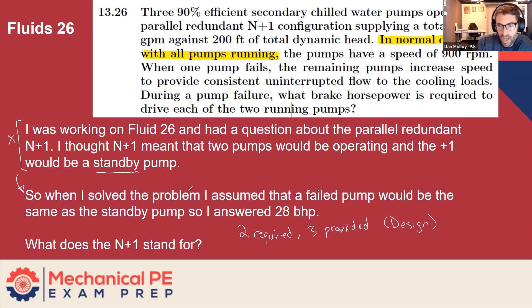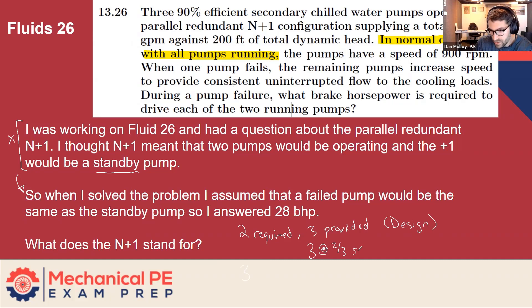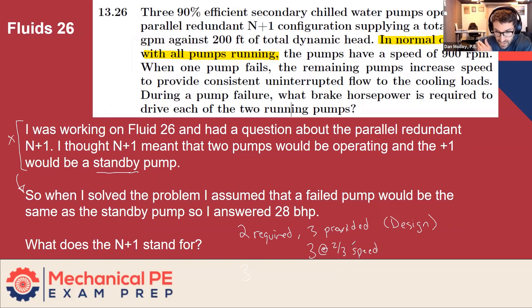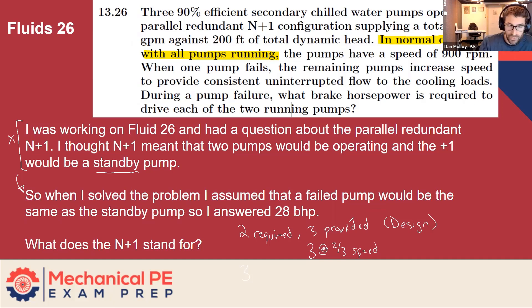Some operations like to have spinning reserve. They'll say run all three, but just run them at two-thirds speed — three at two-thirds speed, so you're achieving the same volume. Then if any one of them fails, you don't even care which one — if they have variable speed controls and you can sense that one has gone down, then the two that remain running will just ramp up to 100%. Both approaches are not unusual — you'll see duty-standby and you'll see variable speed. They're both common.